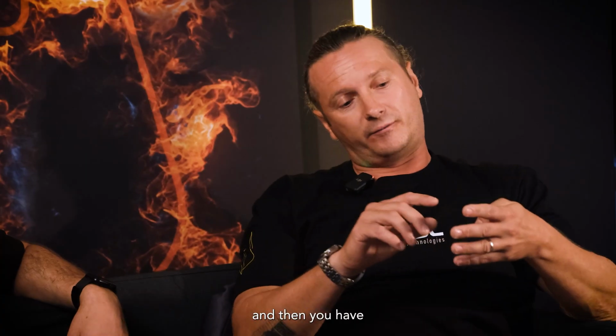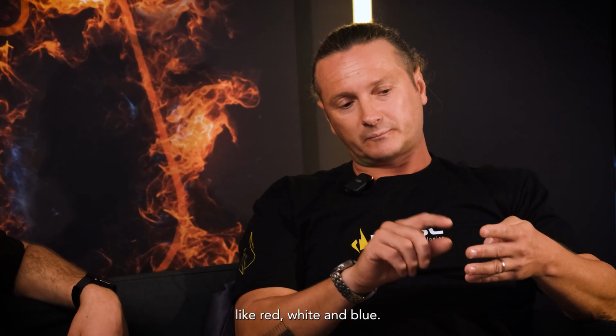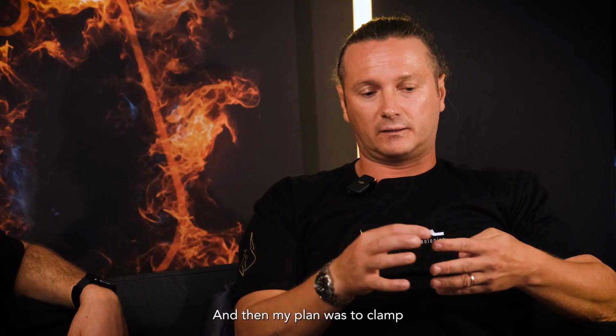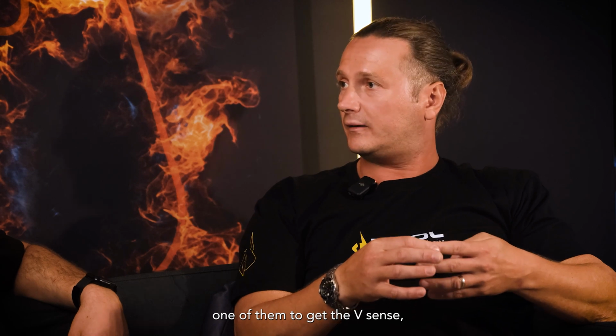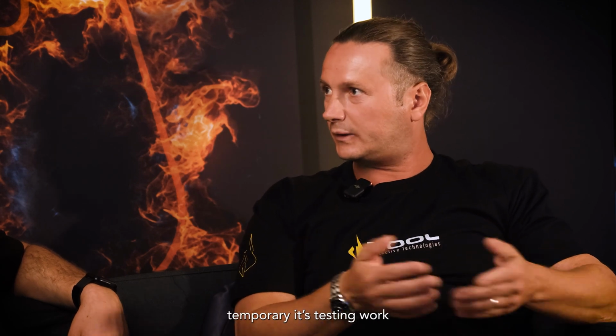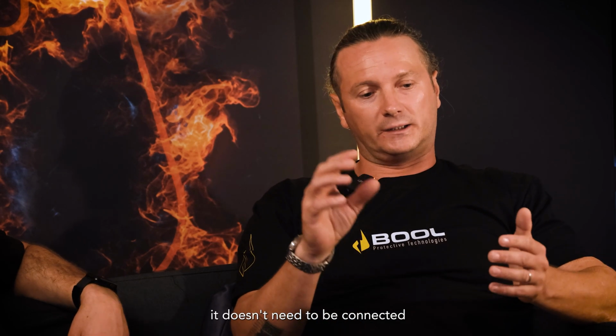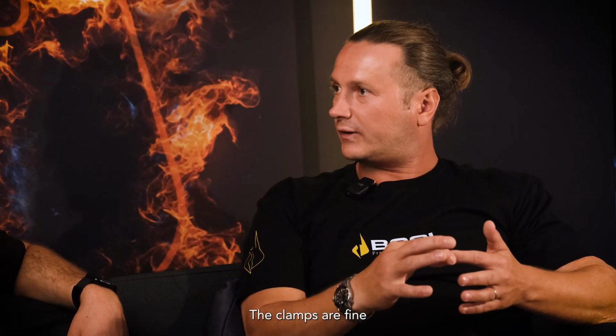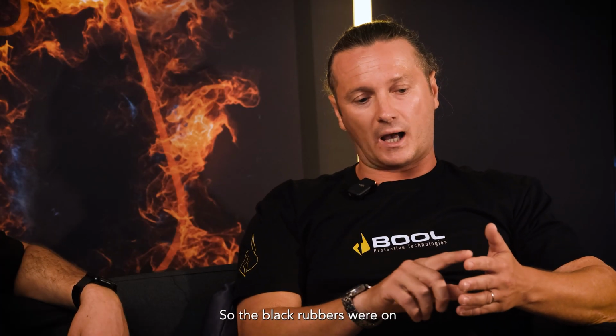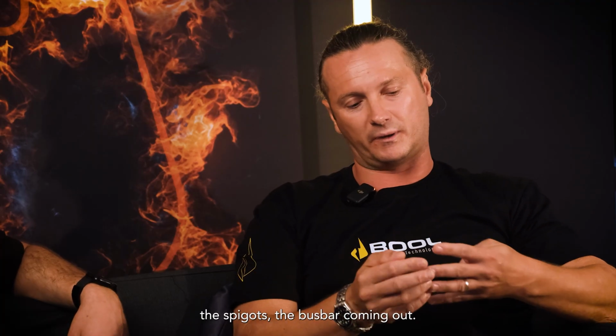There was nowhere to connect onto without switching off. You had a spare MCCB slot, molded case circuit breaker, with red, white, and blue. My plan was to clamp onto them to get the V-sense, because it's just temporary testing work, so it doesn't need to be connected, the clamps are fine. The black rubbers were on the circuit breakers, the spigots, the busbar coming out.